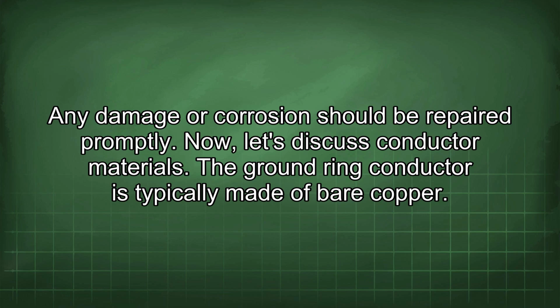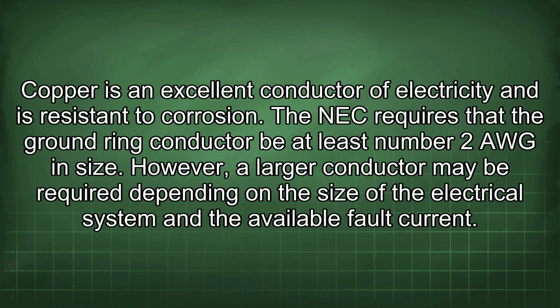Now let's discuss conductor materials. The ground ring conductor is typically made of bare copper. Copper is an excellent conductor of electricity and is resistant to corrosion. The NEC requires that the ground ring conductor be at least number 2 AWG in size. However, a larger conductor may be required depending on the size of the electrical system and the available fault current.